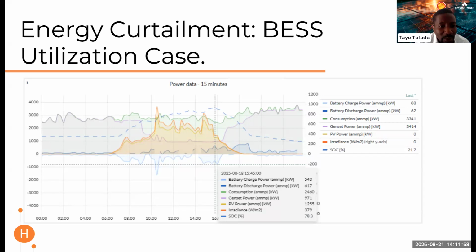So there's a BESS at this site. The broken line is the BESS SOC. It got to 78.3, the highest SOC for the day. So you see that there's no curtailment. The way it works is solar goes up to peak. You can see the solar curve, the yellow curve, matches the irradiance at every point in time, which means it kept the genset at a flat load for most of the day, and all excess energy was going into the BESS. That eliminated curtailment entirely, so it improves solar performance at this site.